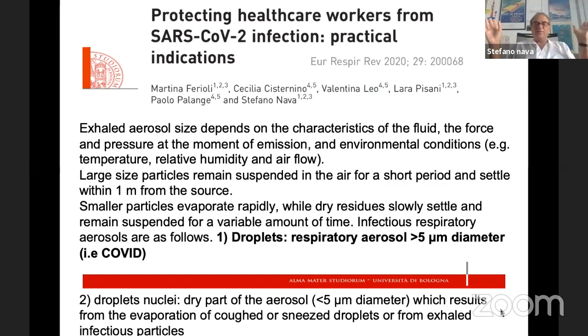When we talk about non-invasive respiratory support, we are talking about droplets. Droplet means respiratory aerosol with a diameter higher than 5 micron, okay? So we need to take into consideration that these particles may remain suspended in the air for a variable amount of time. Well, the World Health Organization stated that when you apply an aerosol device, whatever it is, from aerosol therapy to NIV, patients should be placed in an isolation room with negative pressure, with at least 12 air changes per hour, a dedicated bathroom and possibly an anteroom.